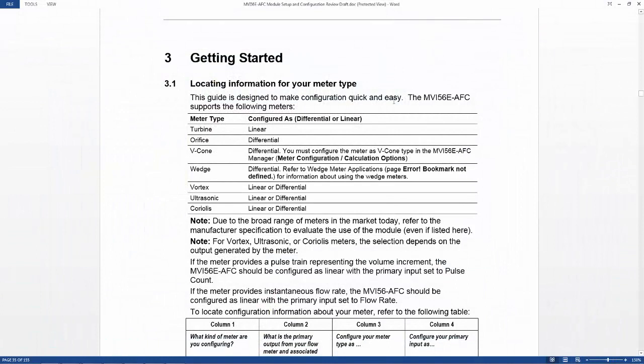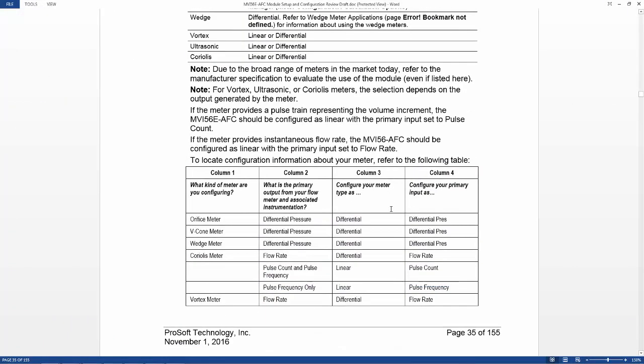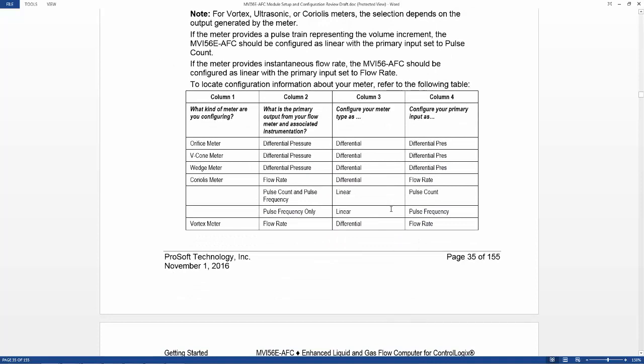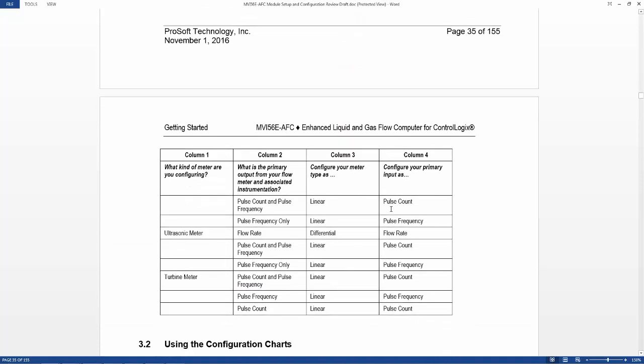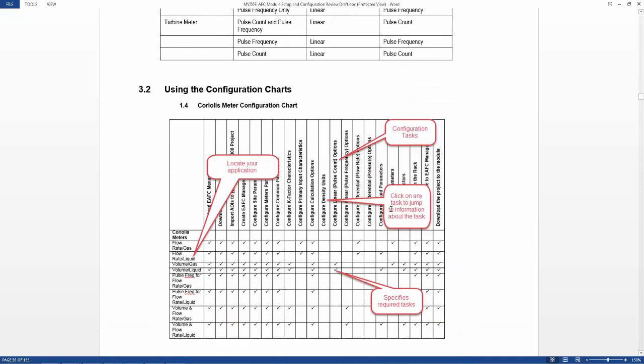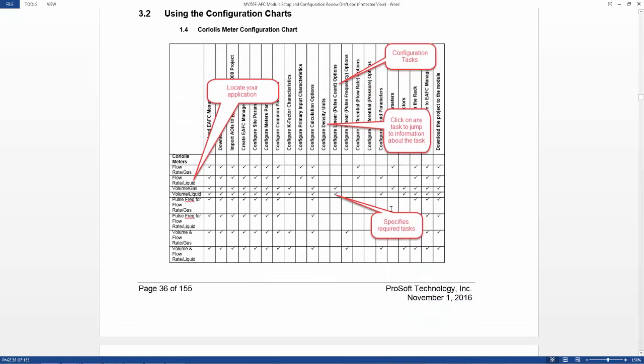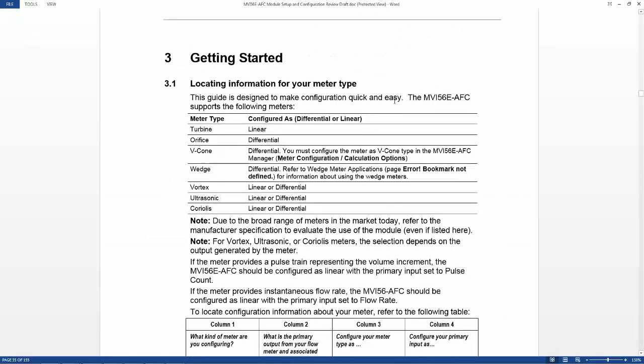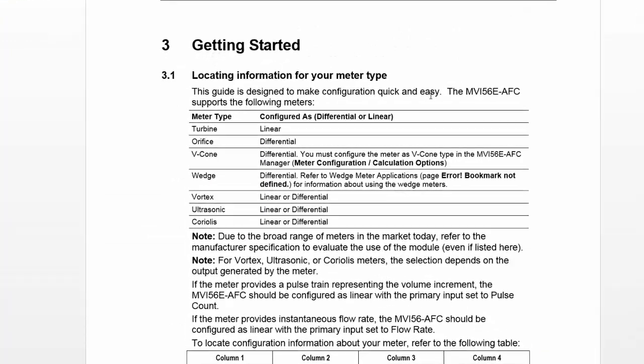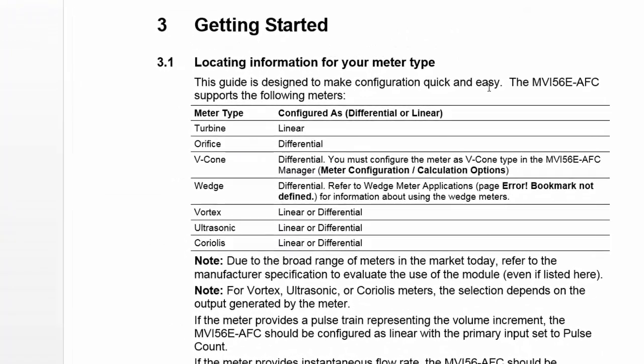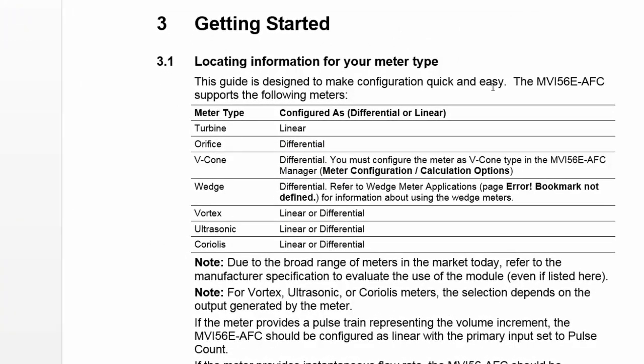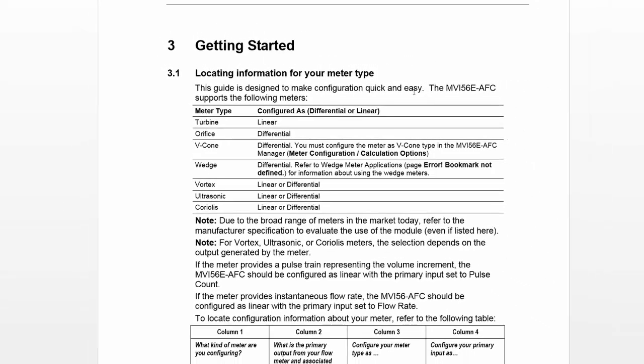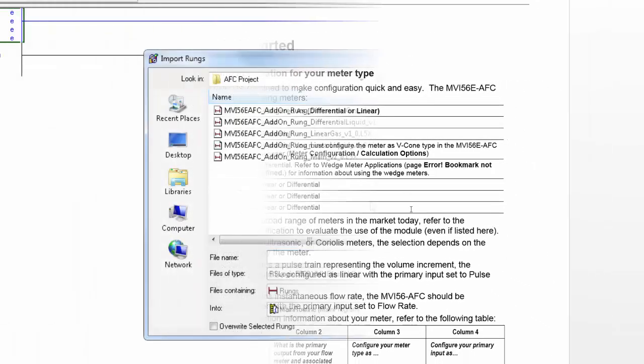Be sure to choose the proper AOI for the type of meter that you're using. Section 3.1 of the MVI56E AFC module Setup and Configuration Guide has a comprehensive walkthrough for selecting the correct meter type. Generally though, for a turbine meter, you would select Linear. For an orifice meter, you would select Differential. V-cone and wedge type meters would also be Differential. Vortex, Ultrasonic, and Coriolis can either be Linear or Differential depending on your primary output.